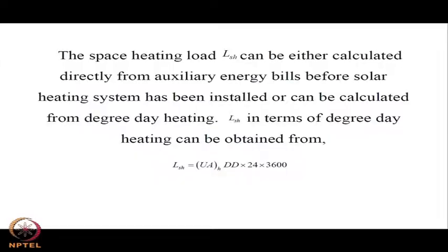You can check yourself, and with the data that is available in the sources that I mentioned, as long as TA bar is less than 15, you can easily estimate the degree days within plus minus 5 degrees. Of course, if TA bar is 20, it does not mean it does not require heating. You may need both heating as well as cooling, okay, daytime cooling and nighttime heating.